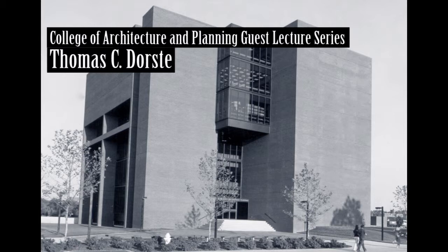Let me just find another one here. Then all of this leads us into the problems of retrofit and what you can do with existing buildings. We've worked for about 10 years at Taylor University in Upland, Indiana, and studied Williams Hall, which is a men's residence hall built about 15 or 20 years ago. We went through it. We found out what they were doing. We discovered things that could be done to the building. Roof insulation addition, reduced the window area, didn't put in thermopane, increased the wall area, increased the insulation in the walls and infiltration control, changed the heat gain and heat loss, changed the makeup air system in the kitchen, and wound up with a savings.